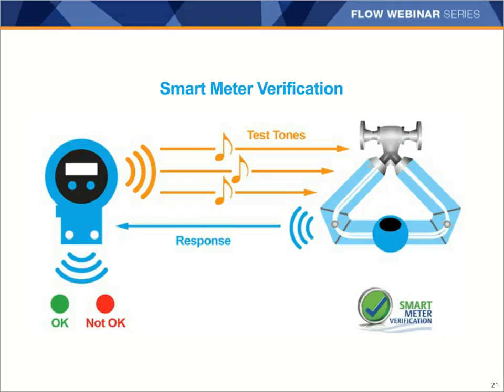So when the meter is installed in the field later, a simple push of the button allows the same test to be performed and the results to be compared to the fingerprint. Within minutes, without stopping the flow, without exposing personnel to the process, or removing any flanges, the health of the meter can be tested. This has significant safety benefits even when it isn't installed in an official SIS. However, when used in conjunction with SIS, this diagnostic can actually be used to improve the proof testing.